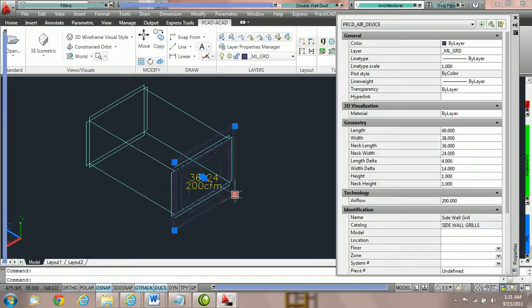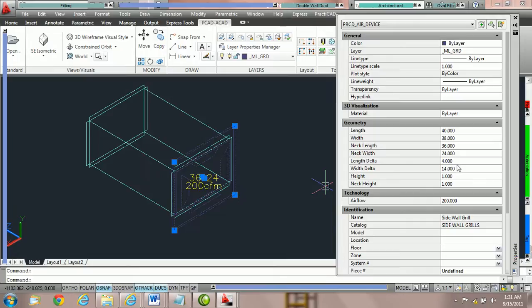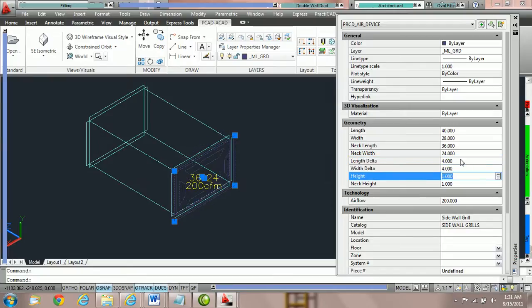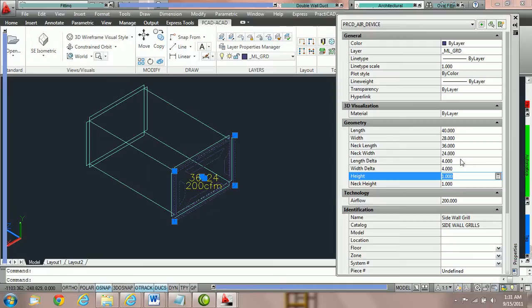Double click on the fitting. Go to the AutoCAD property box and give the length delta, width delta, whatever you want. If we want a two inch flange all the way around, we'd actually type in four and four. That would mean that we've got two inches on each side or four inches of total delta.